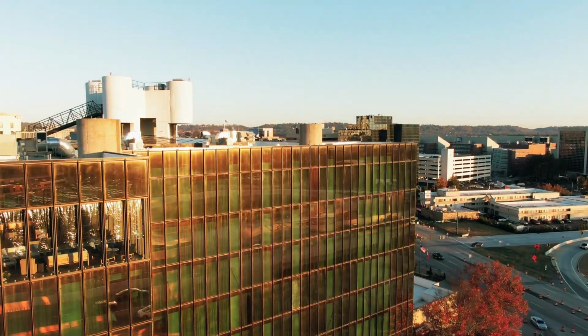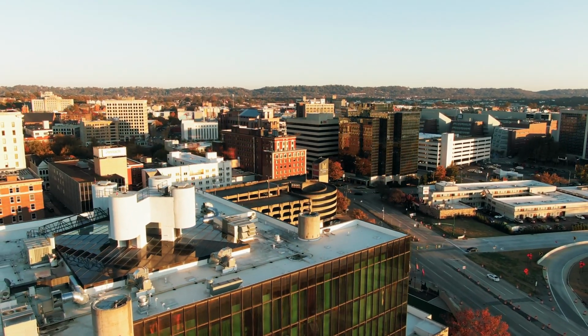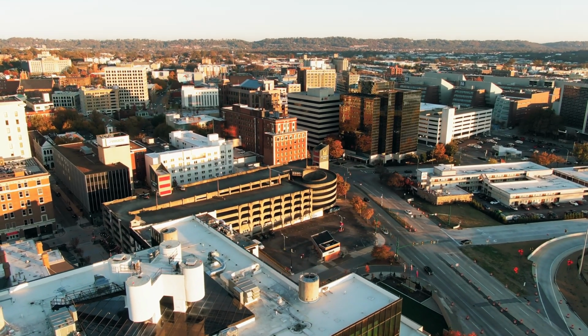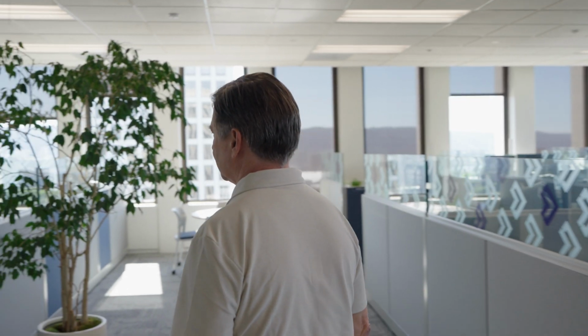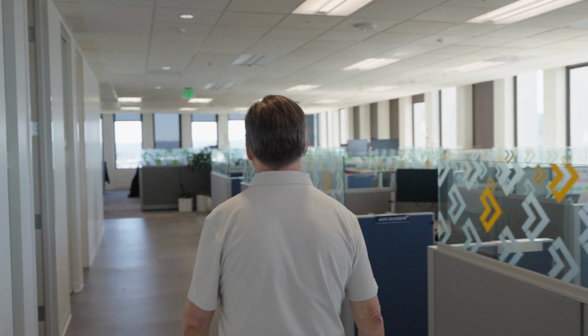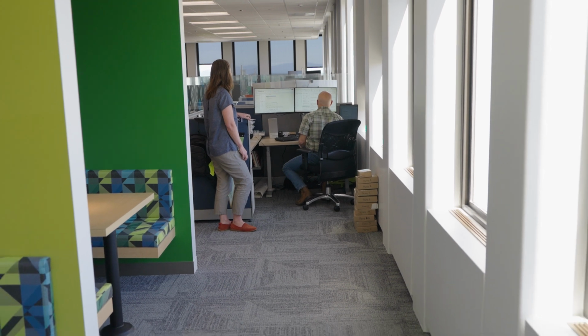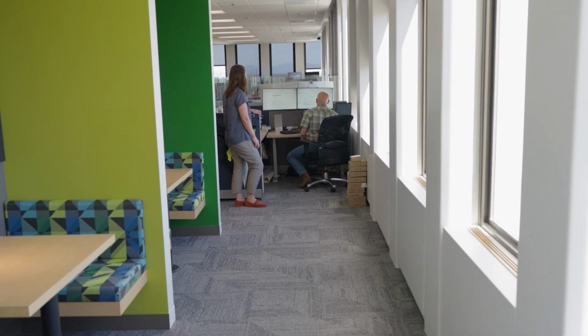to work together well. VHE DOAS aims for a higher energy recovery level and focuses on sensible heating, because eliminating post-heating in Climate Zone 4 can allow us to simplify our systems and maximize energy efficiency savings. Washington State Energy Code's Advanced Energy Credit is the same requirements as VHE DOAS, and it's an easy way to get a lot of those required points. Especially when we're talking about new construction, depending on your fuel type and your occupancy type, you can get more than half of your energy credits by going that route.